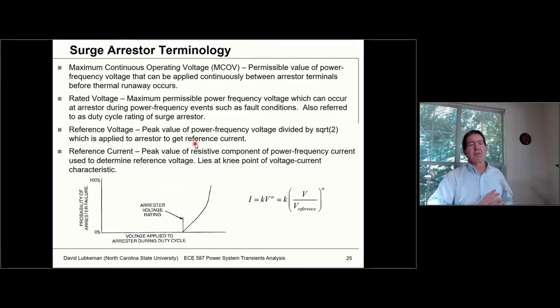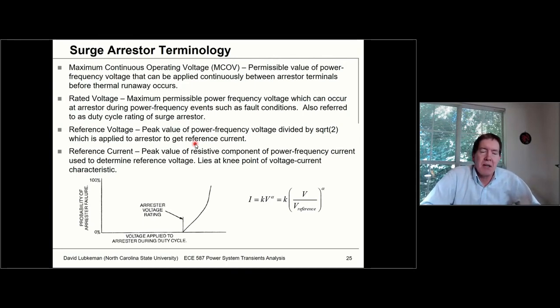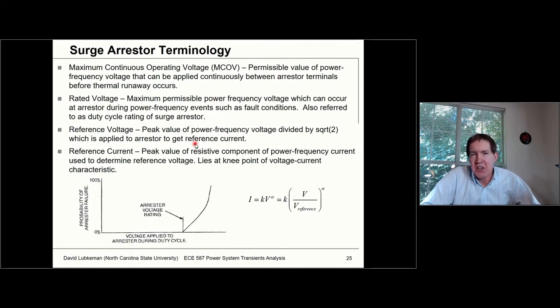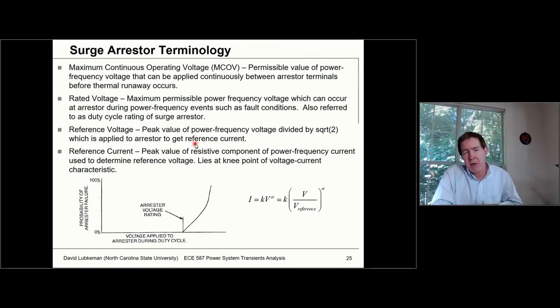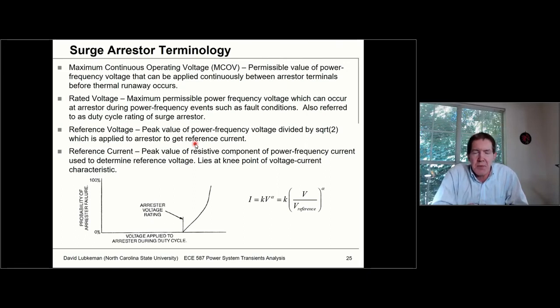As far as surge arrestor terminology, there's maximum continuous operating voltage (MCOV). With these nonlinear devices, you need to keep the voltage below a certain level; otherwise, you start drawing current which heats the device up, drawing even more current — a thermal runaway effect. We need to size the arrestor so that MCOV is not violated under normal conditions.